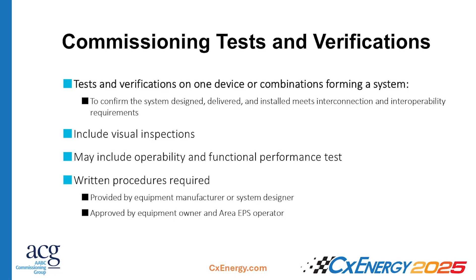There are different levels of commissioning tests being done. Each manufactured device, typically inverters, but also breakers and transformers, the vendor will make sure their equipment is operating properly, so they have their own list of commissioning requirements. That list may or may not line up with what we're talking about here. For instance, with a transformer or switchgear, they're used to doing switchgear testing, but not interconnection testing for these requirements, so we have to make sure it all lines up.